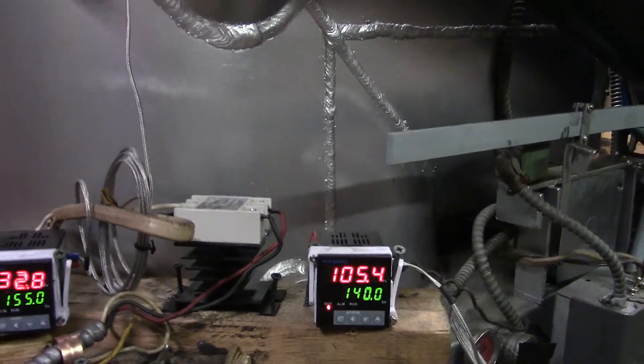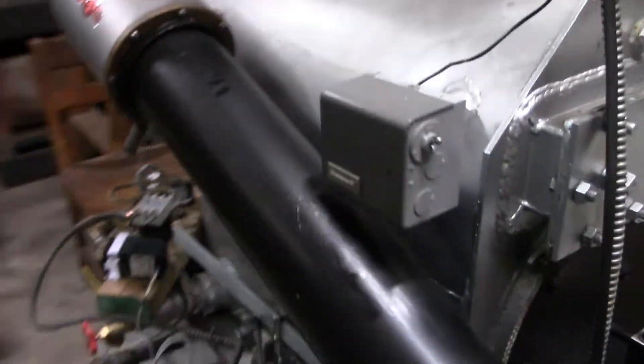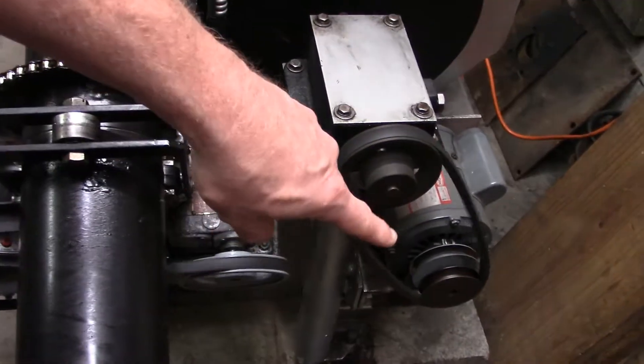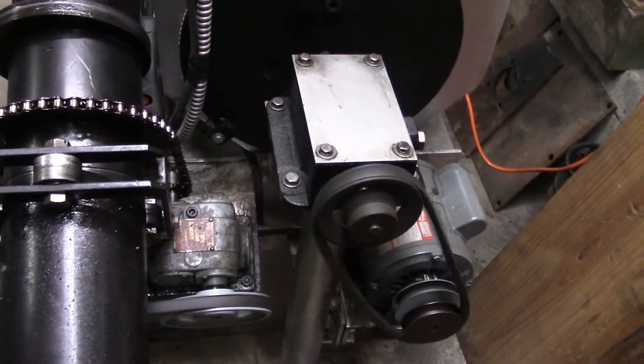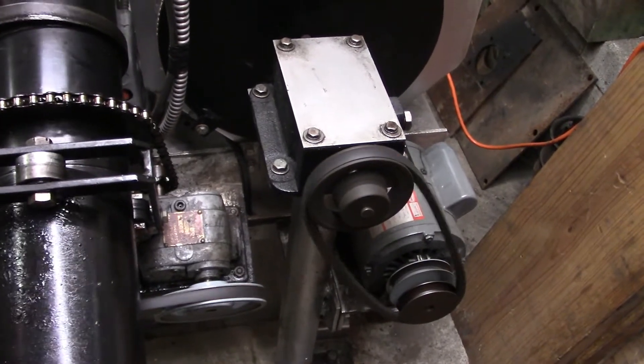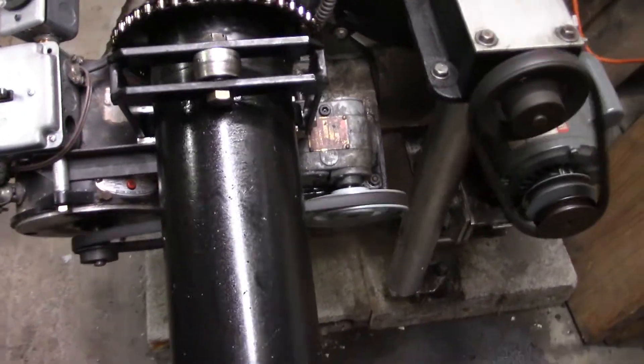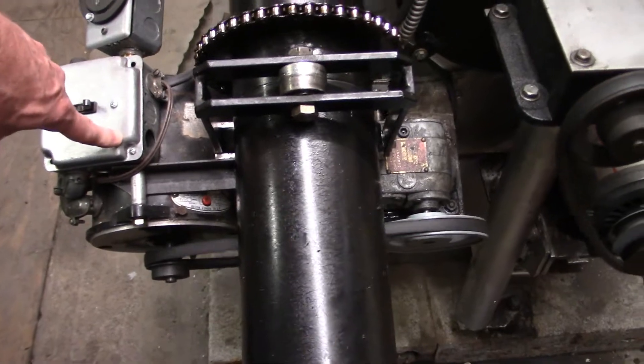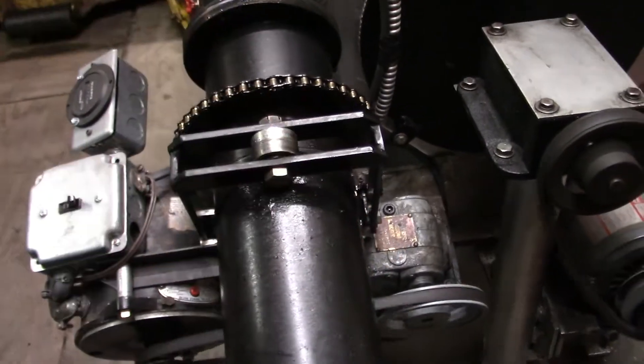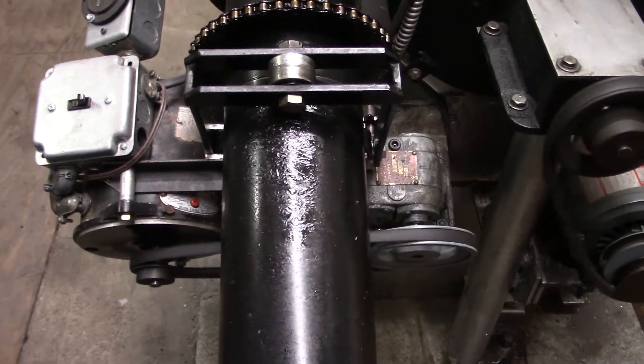It just started up for a heat call. We're running a very low fan speed — it's not really heating anything right now. We have a three-inch pulley on the motor and a four-inch pulley on the fan, which gives us somewhere around 1,300 RPM. For the auger we have a two-and-a-half-inch pulley on the motor and a five-inch pulley on the gearbox.